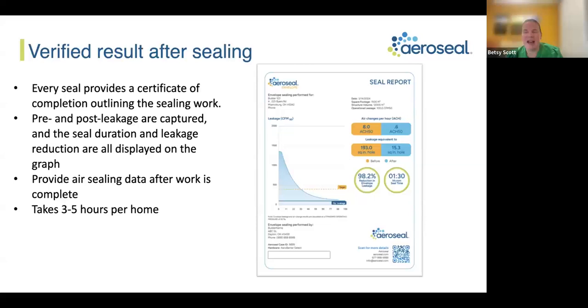And then how does it work with occupied units? We like to call those rescues. Aeroseal is really best done in new construction. We have done it for builder partners who didn't use it to start, and before we got involved they were failing. In that instance you have to cover up any horizontal surfaces. Anywhere there's an air pull vertically, it'll start to seal and coagulate. If it doesn't do that, it just falls to the ground and kind of turns into a drywall dust within 30 minutes.